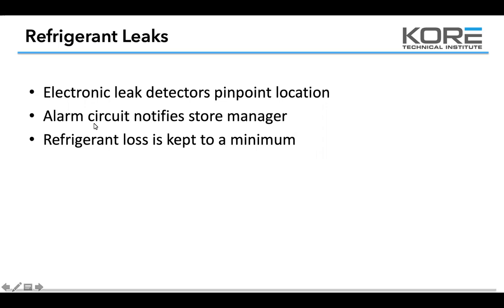If you guys need an H10 for your branch, please give me a call — that's the KORE recommended leak detector by choice. Alarm circuits notify the store manager when dealing with local leak detection. Any racks now are required to have local leak detection. Whenever you're in the controller, make sure the leak detection is working — this is a critical pain point for customers. If they find out their leak detection is not working, they're not happy. They're required by the EPA to have electronic leak detection over a certain threshold of pounds held in the system.